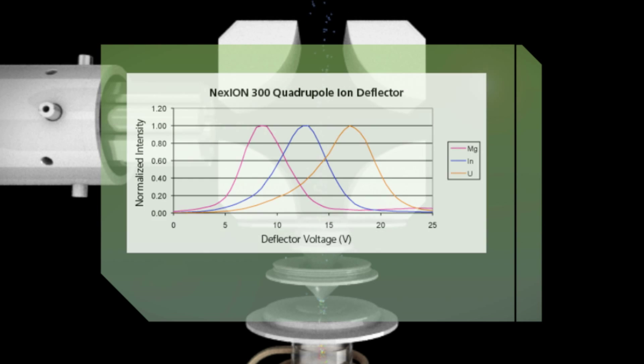The quadrupole ion deflector is the only filter of its kind that allows you to adjust your mass bandpass on the fly, automatically, to maximize sensitivity for every element in a run.